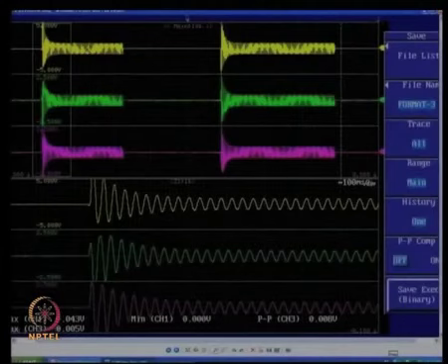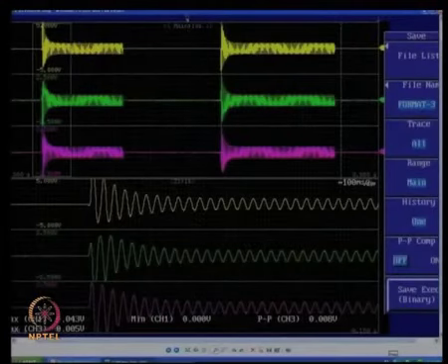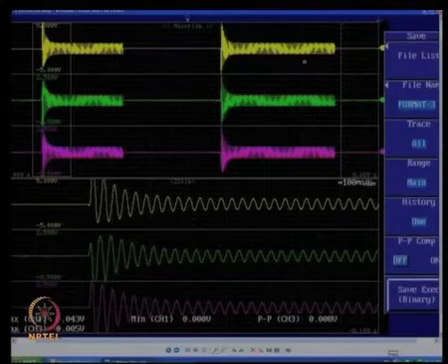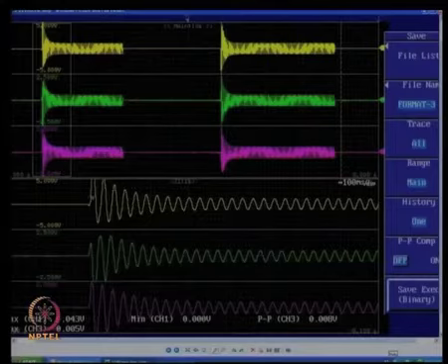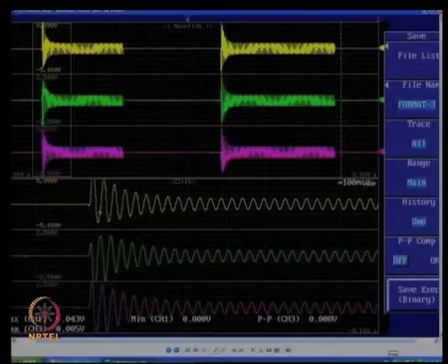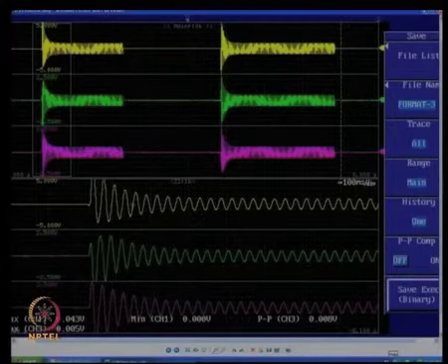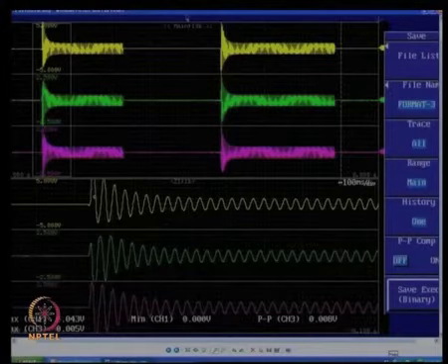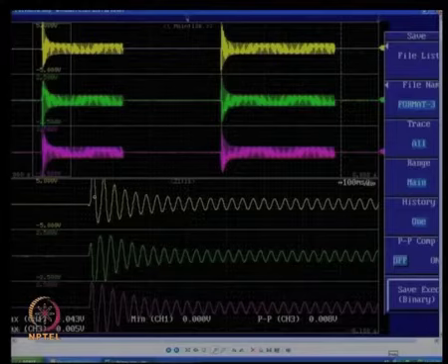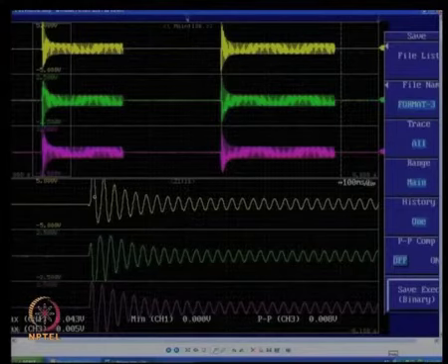This is what we actually captured. We gave a short, then removed the short by opening the MCB again, and gave another short. We actually did it twice. One of the things you will notice in the waveform, this expanded part shown below, you will see that there is a DC offset as well as the sinusoidal envelope is quite large in the beginning. The DC offset in all the three phases are not the same; it depends on the instant at which you apply the short circuit.